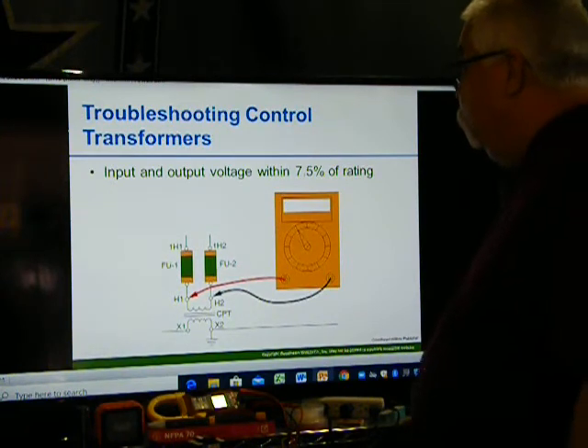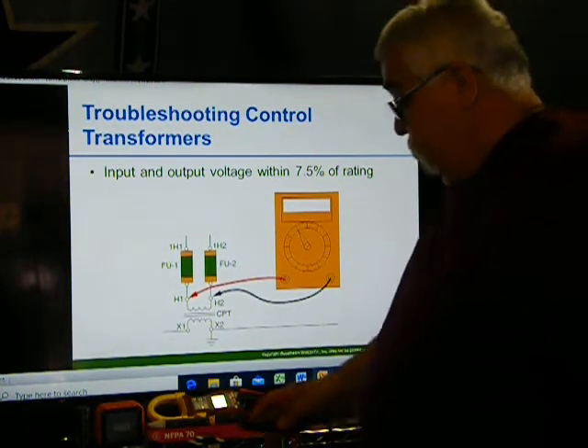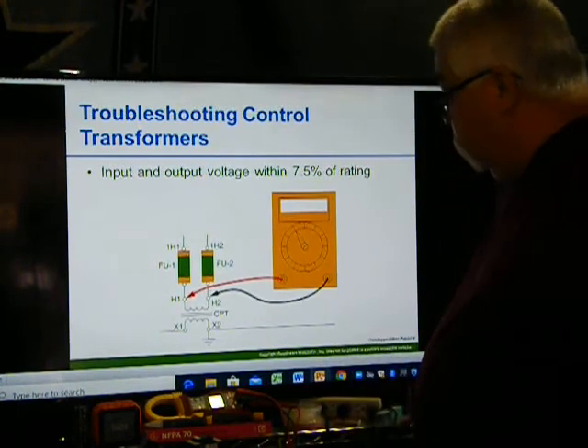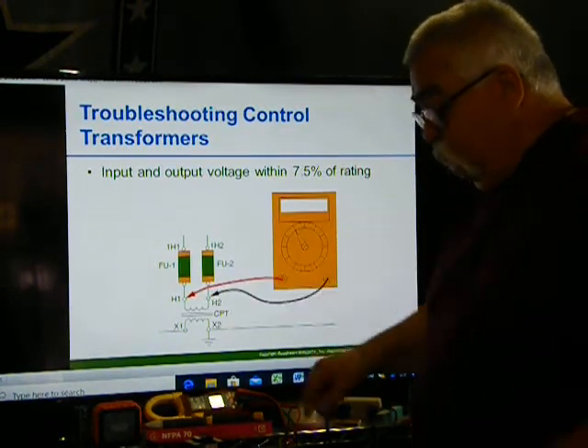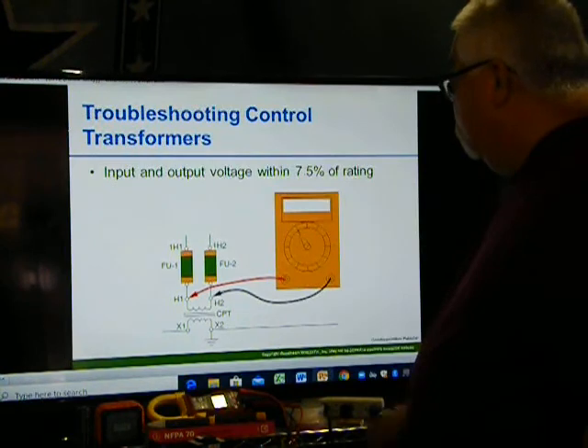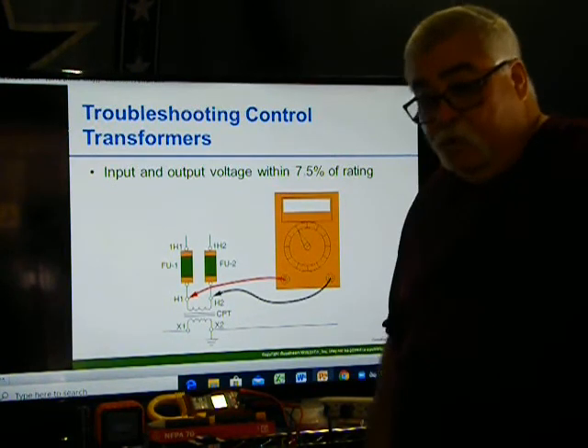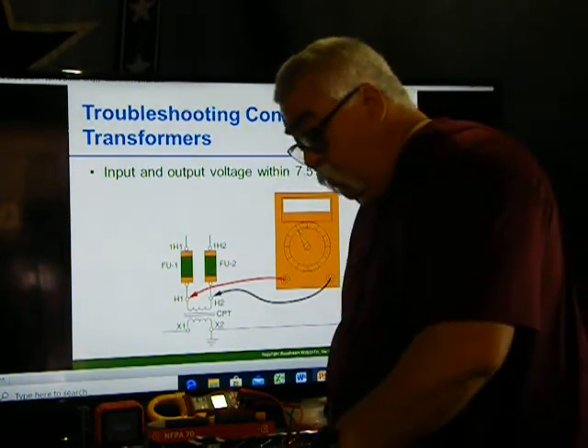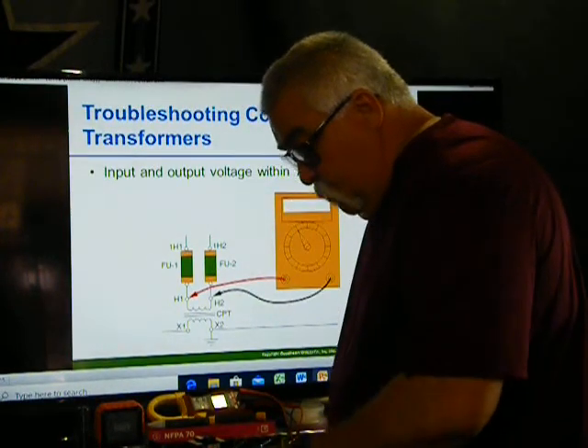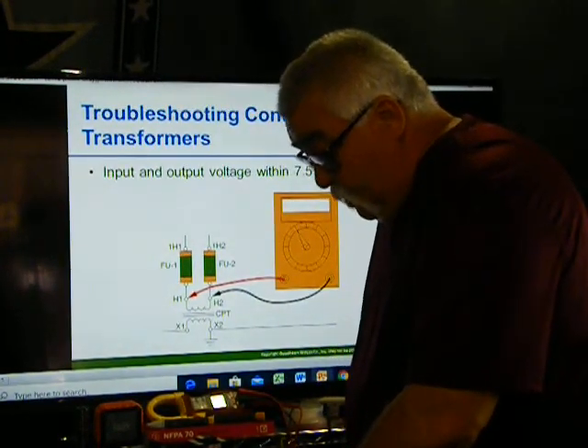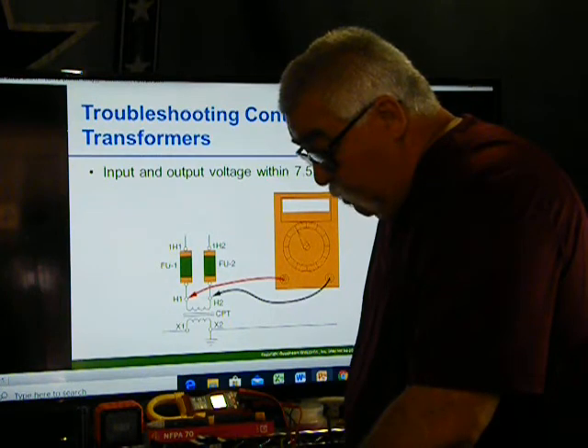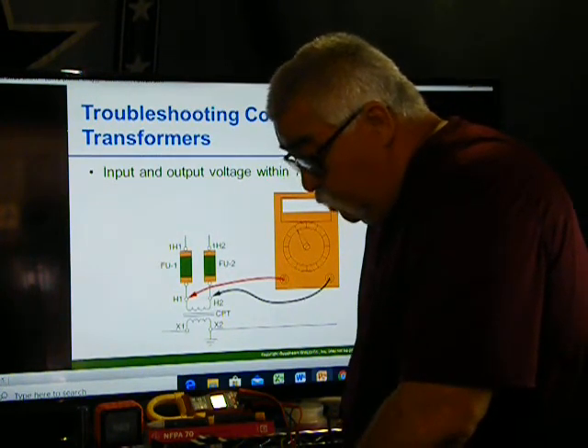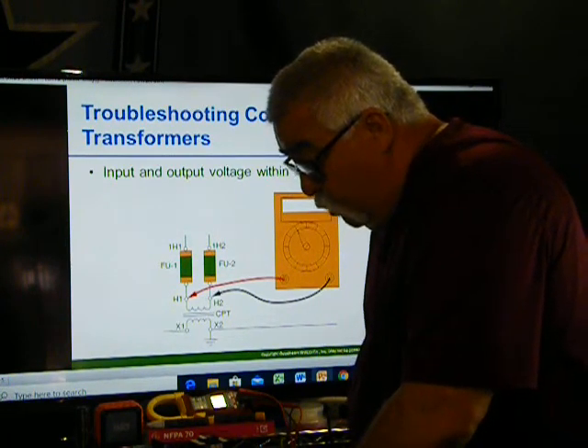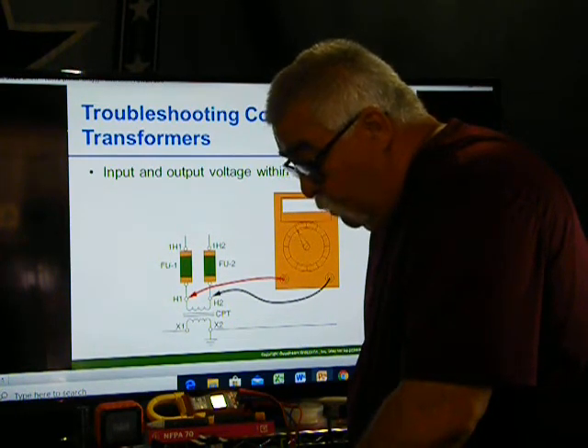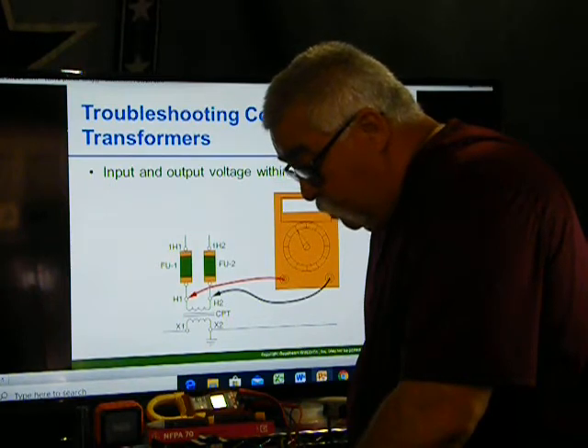Troubleshooting control transformer. When you're testing the transformer, when you're going across the transformer, your input voltage should be within 7.5% of the rating. So they gave you sample problem 18.1. It says the control transformer, which steps voltage down from 480 to 120, is being tested. What are the acceptable voltage readings for the input and output voltage?